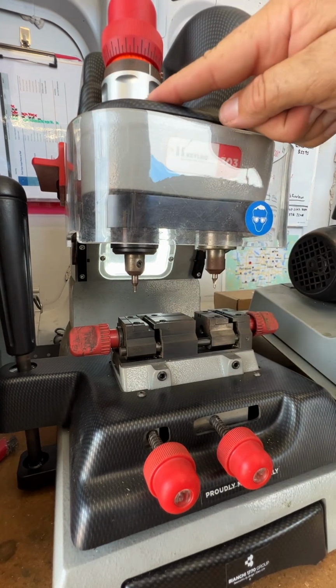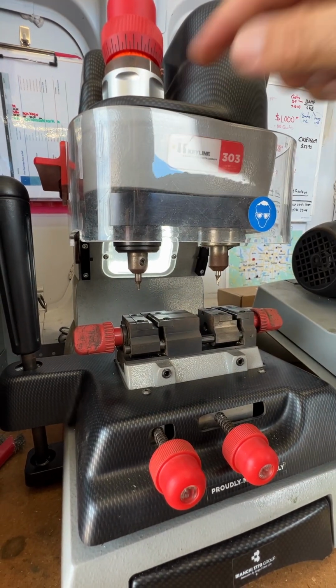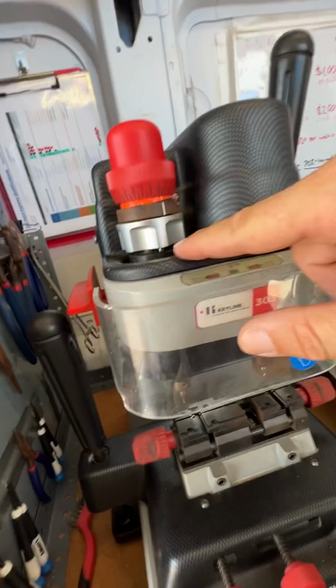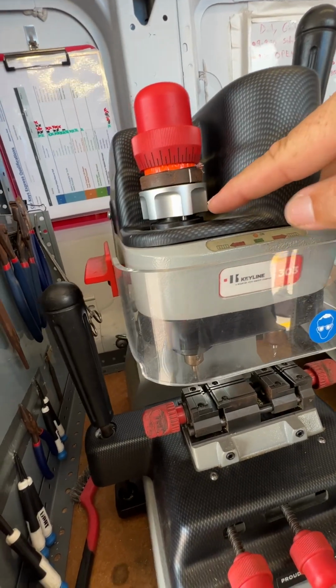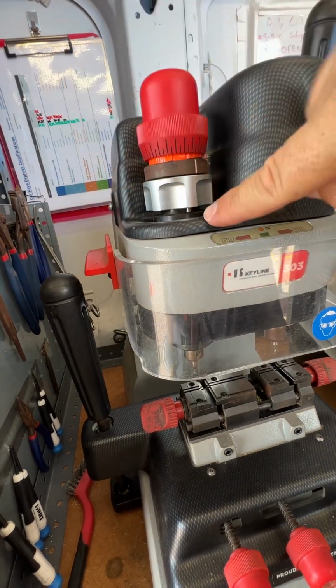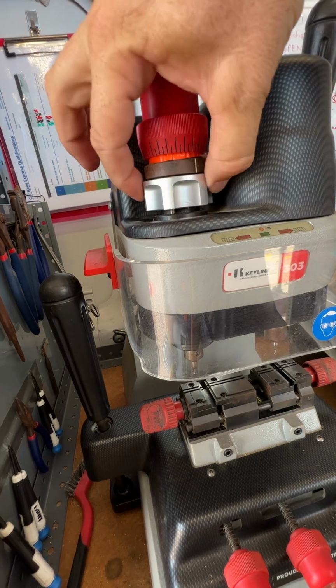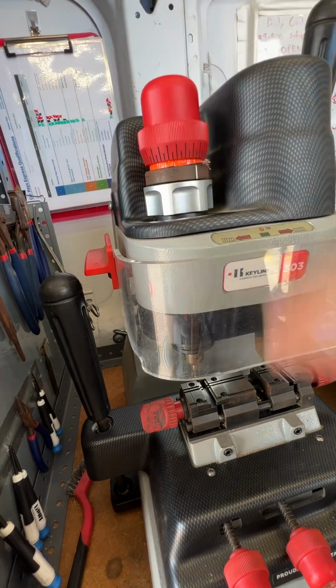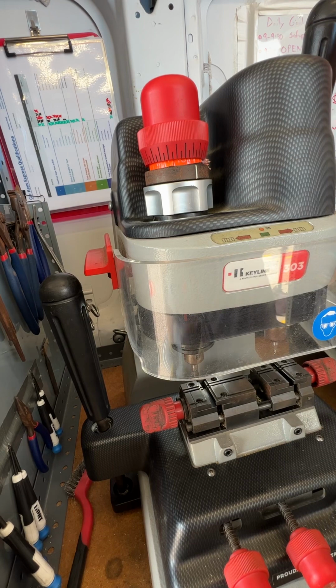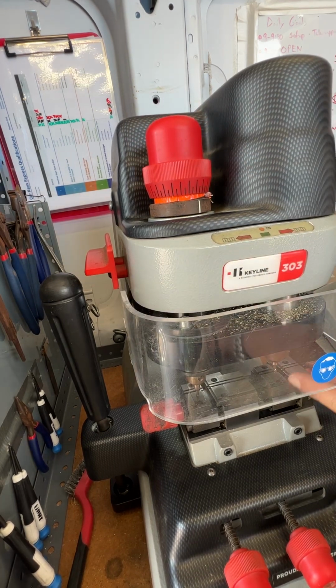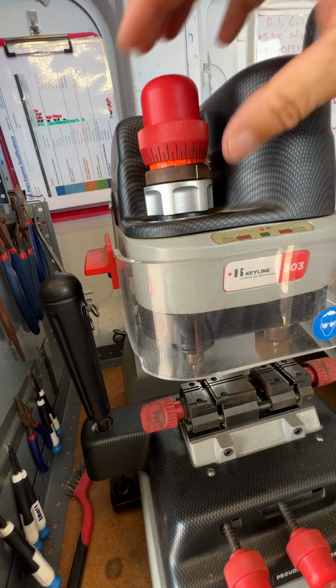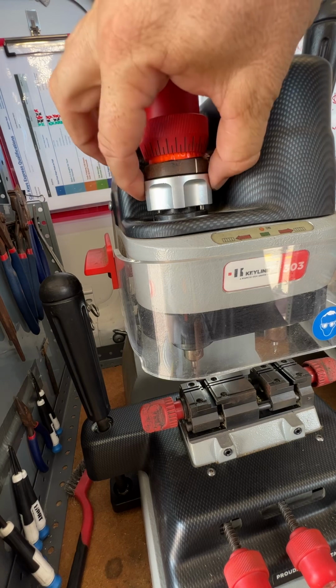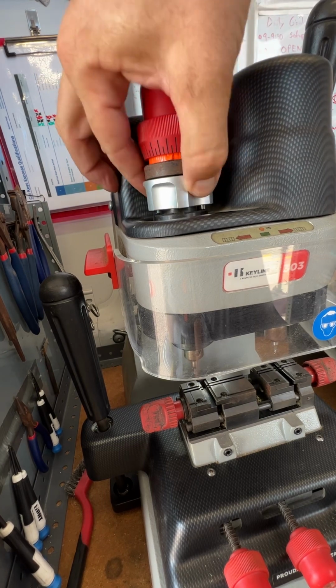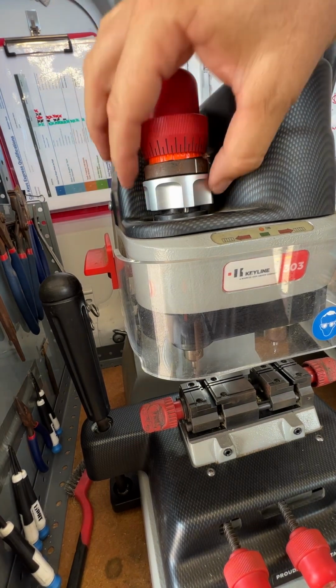Now also, pay attention to the tracer. If I move this, there's going to be this little knob. Let me raise up. So this little knob here. So if I turn the silver, see the little knob there, it will drop down and now everything's shifted. So now if I, without changing this, pull down, it is way off. I have like 1/8 of an inch difference. And if I adjust it, it's not going to work. So what I need to do is lift this up. See how it drops down?